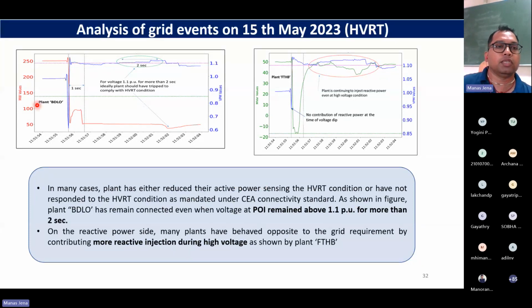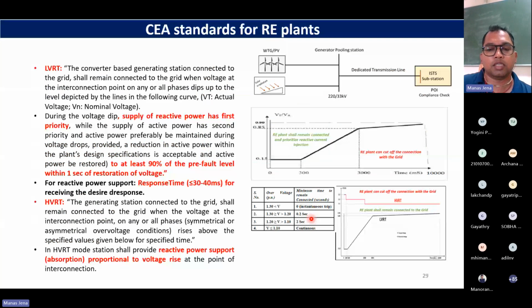As shown in this particular figure, this plant BDLO has remained connected even when the voltage at the POI remained above 1.1 per unit for more than 2 seconds. Here is the point of interconnection voltage. You can see this is the 1.1, so it is more than 1.1, and as far as our table is concerned, okay, it should remain 2 seconds, 1.1 to 1.2, the limit is 2 seconds, right?